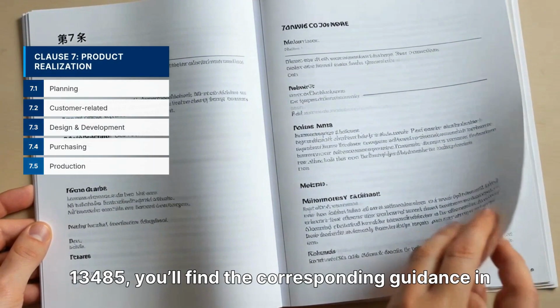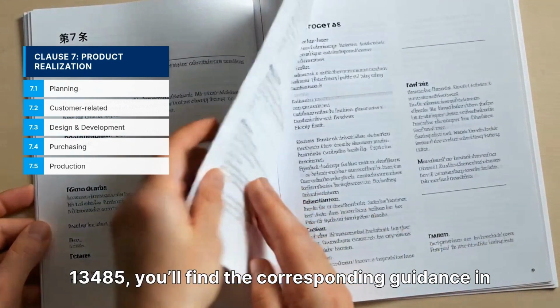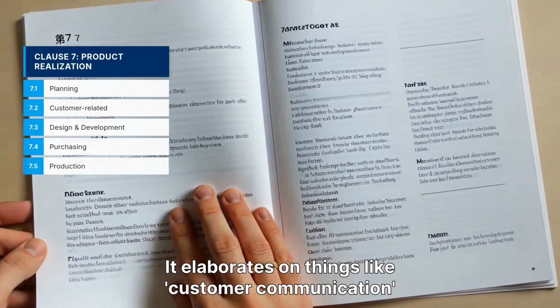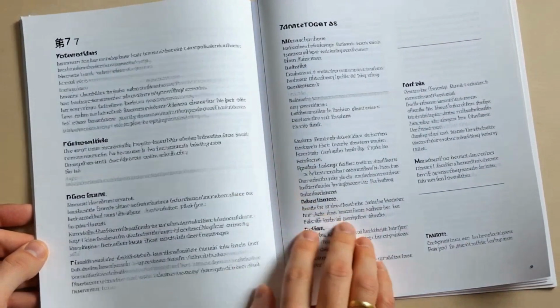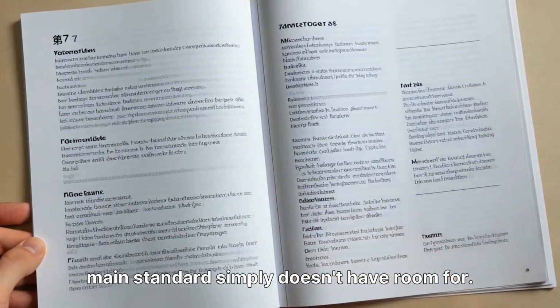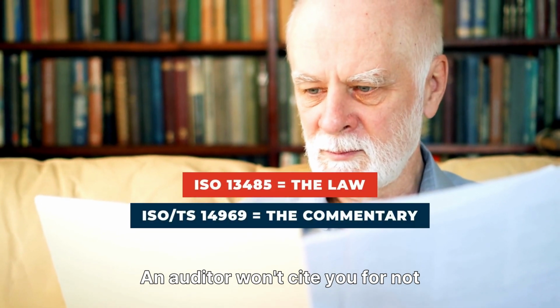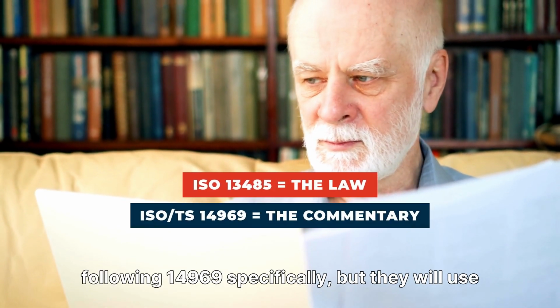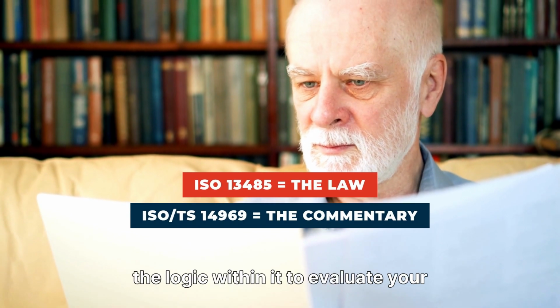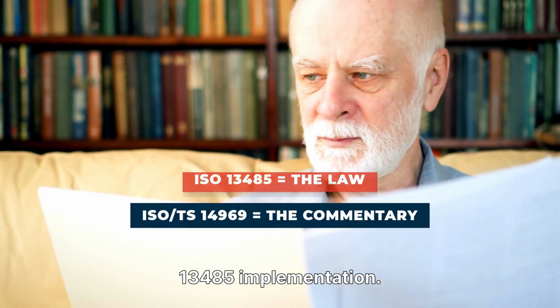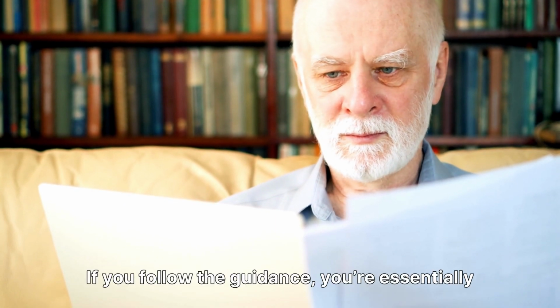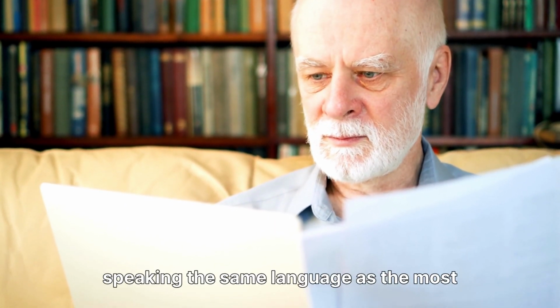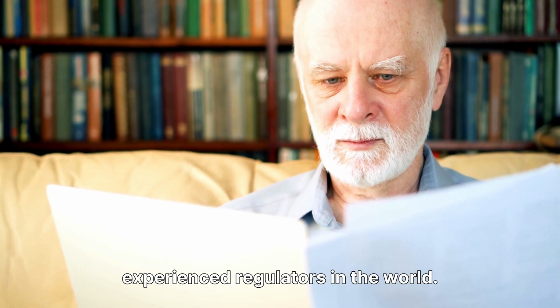production. If you look at Clause 7, Product Realization, in 13485, you'll find the corresponding guidance in Clause 7 of 14969. It elaborates on things like customer communication and purchasing controls in ways that the main standard simply doesn't have room for. An auditor won't cite you for not following 14969 specifically, but they will use the logic within it to evaluate your 13485 implementation. If you follow the guidance, you're essentially speaking the same language as the most experienced regulators in the world.